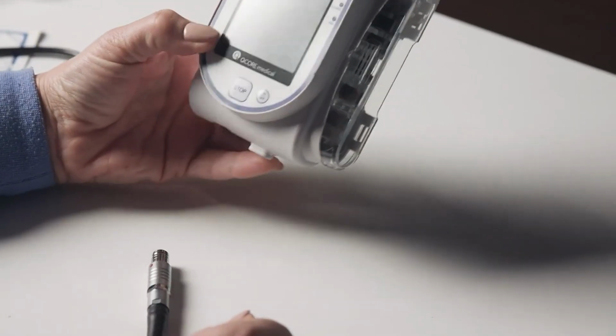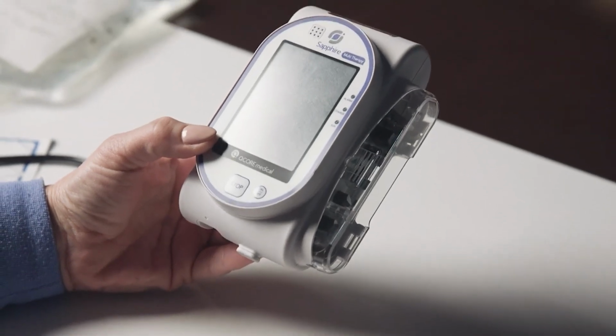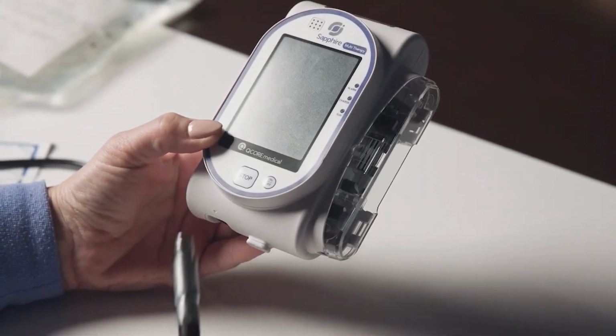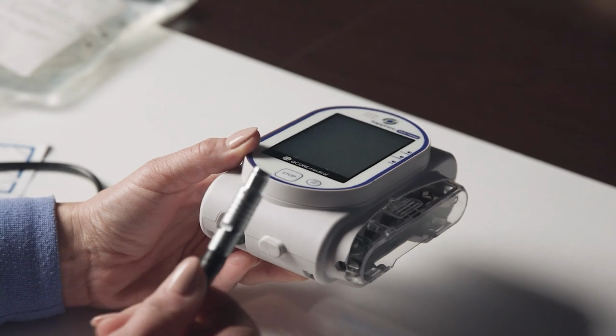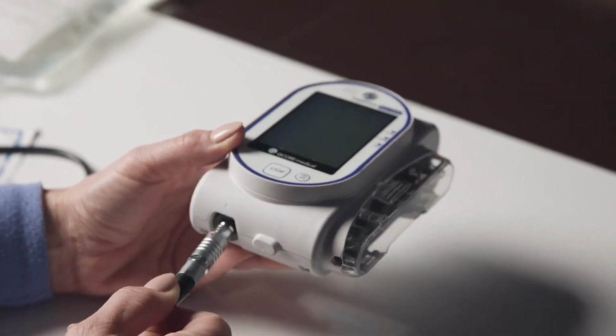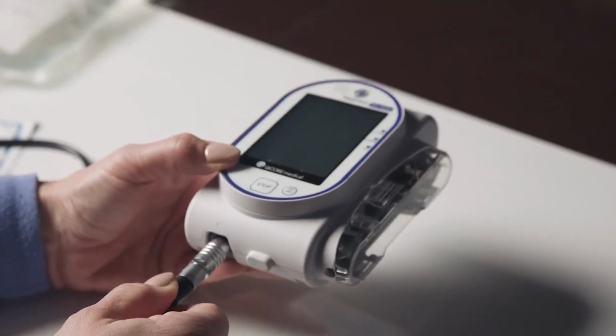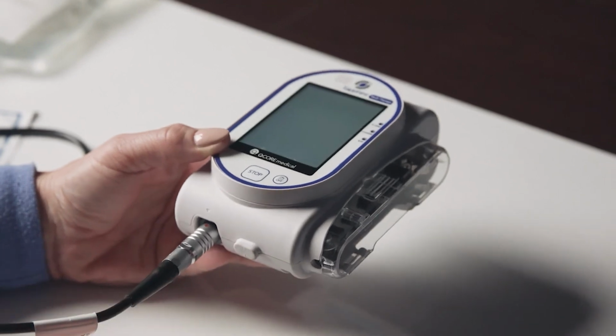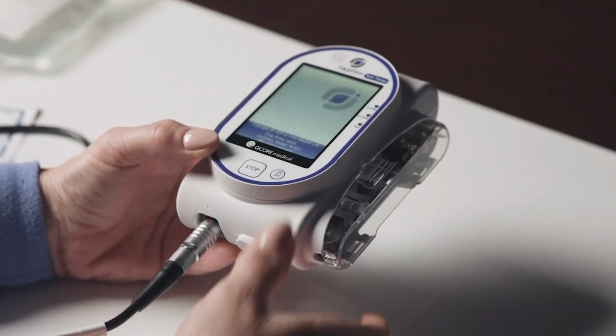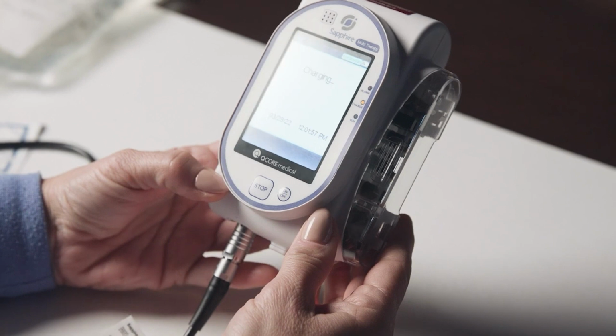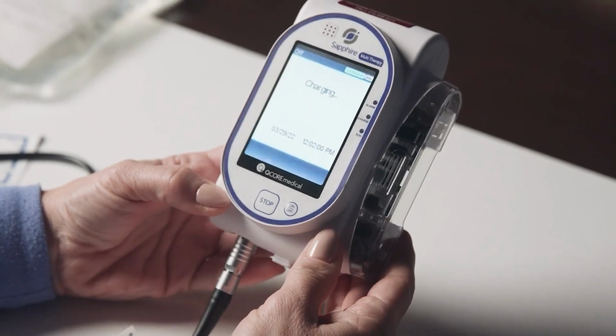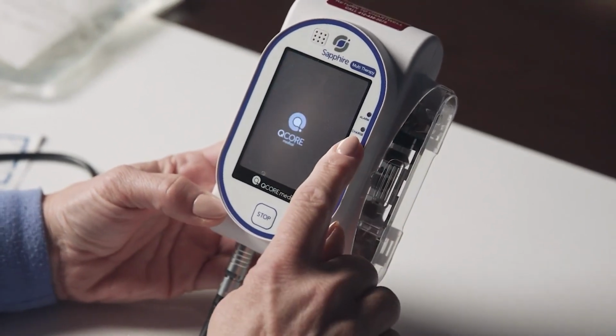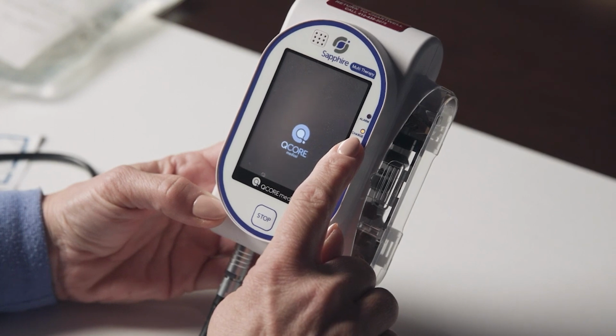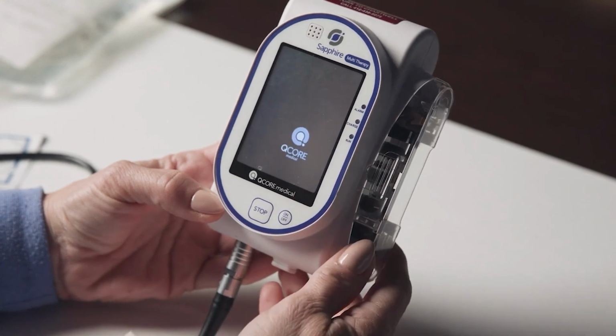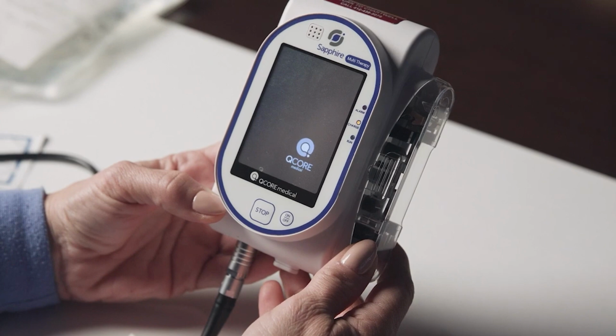You will need to charge your Sapphire pump's internal battery with the charging cord that came with your pump. Plug the power cord into the Sapphire pump by lining up the red dot on the cord end with the arrow at the bottom of the pump as directed. Be careful not to twist or turn the cord while plugging into the pump. Instead, push the cord directly in. The yellow charge light will blink to indicate that the pump is charging and will remain steadily lit when fully charged.